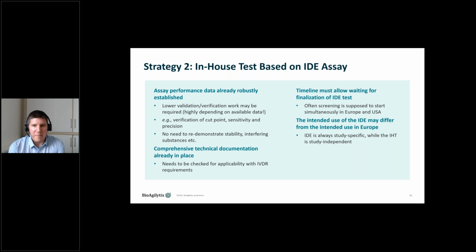The second strategy is a scenario we're also facing quite frequently, where the assay has already been established in the US following the IDE approach. This means that in these cases, a lot of data is already robustly established following design control. So if we go with that strategy, there may be significantly lower validation or verification work to be done.